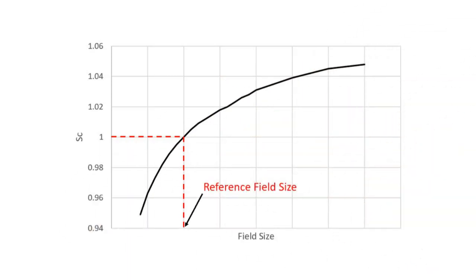If you measure the collimator scatter factor for multiple field sizes, you'll get a plot that looks something like this. For field sizes smaller than the reference field, the collimator scatter factor is less than one. But for field sizes greater than the reference field size, the collimator scatter factor increases above one. By definition, the collimator scatter factor for the reference field is one.